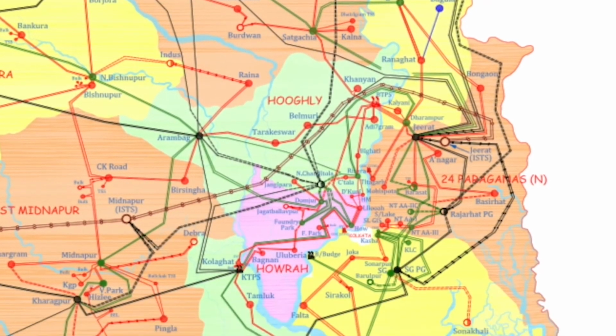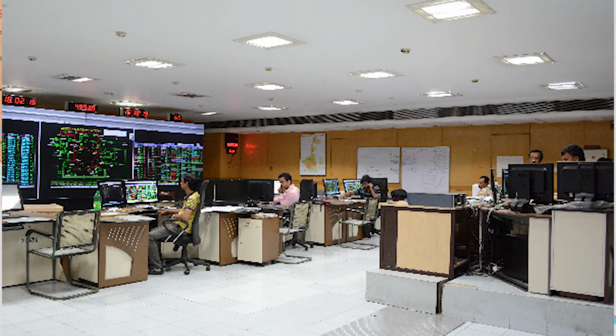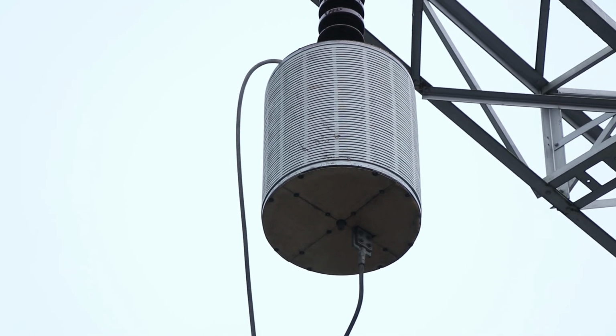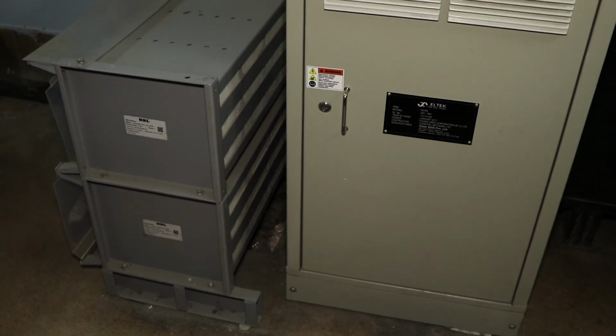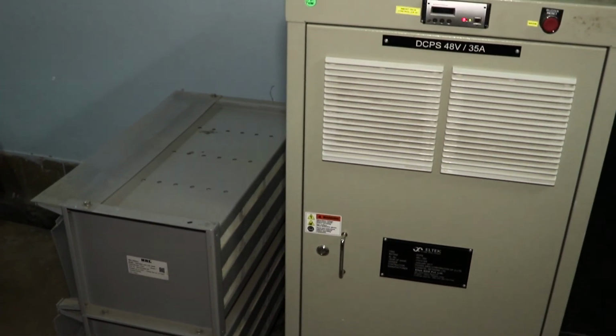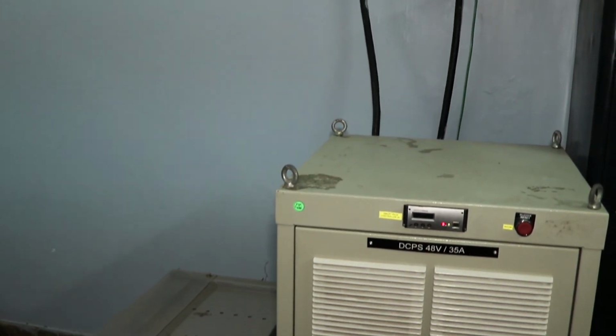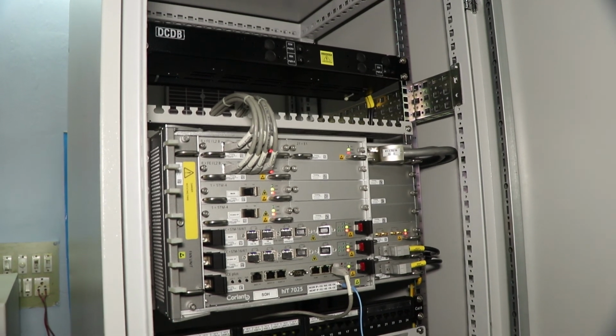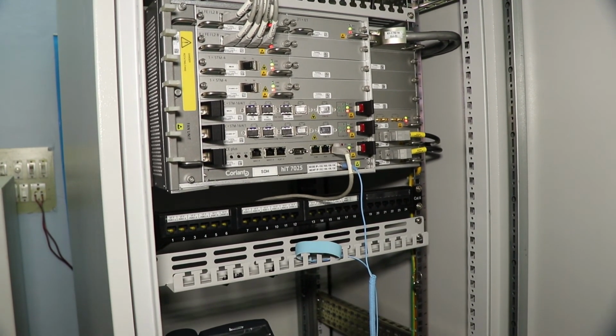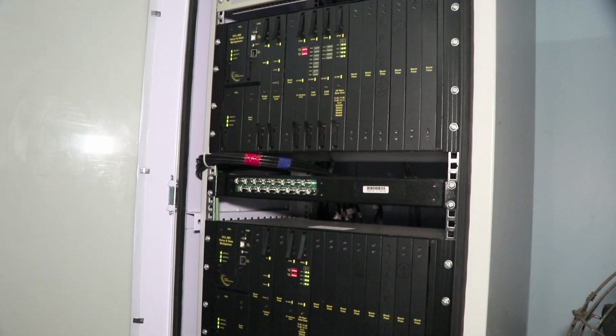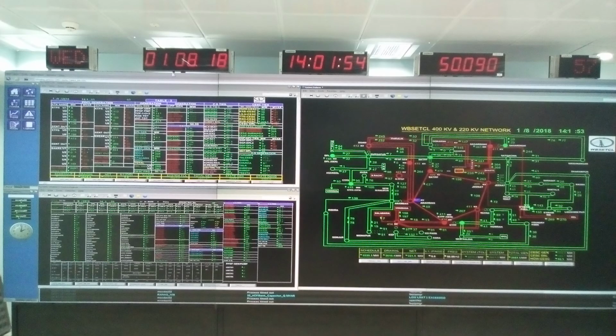For substation to substation and SLDC direct communication, we are using power line carrier communication system, which gets its DC supply from a 48V DC battery bank through a 48V DC battery charger. For modernization of the communication system, we are installing optical fiber and its associated control panels. SCADA is also used for supervision and monitoring purpose. In OPGW technology, we are replacing our existing ground wire on transmission towers with optical ground wire cable. Using this technology, real-time monitoring of our substation data will be more reliable.